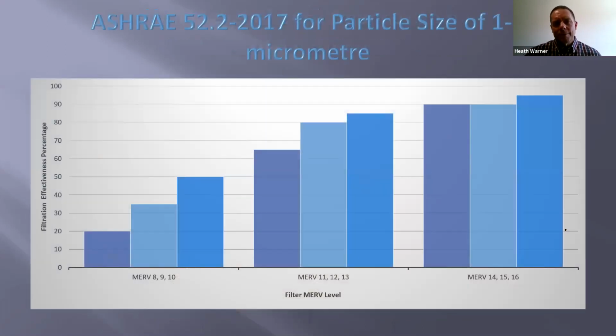Industry standard is ASHRAE 52.2. That particle size of 1 to 3 micrometers, that's for a regular dust particulate. Even though in the graphic that we showed earlier you can get a MERV rating of 1, real filtration that you'll see here does not begin until MERV 8, 9, or 10. When you get up to MERV 8, 9, 10, you start talking about actually having dust filtration. In this case, MERV 10 is right about 50% of all dust. MERV 11 actually bumps that up to 65, and then so on and so forth, clear up till where you can get almost 95% of particulates if you go clear up to MERV 16, which sounds really good. It's a good case for having filtration on your job site if you can get to it.